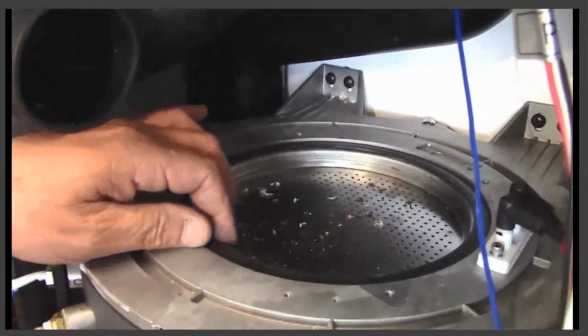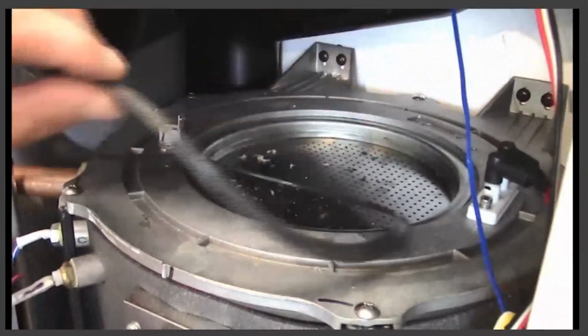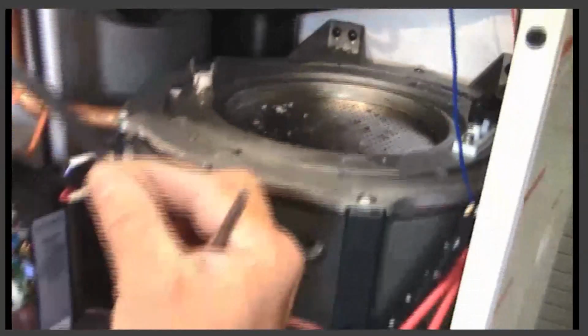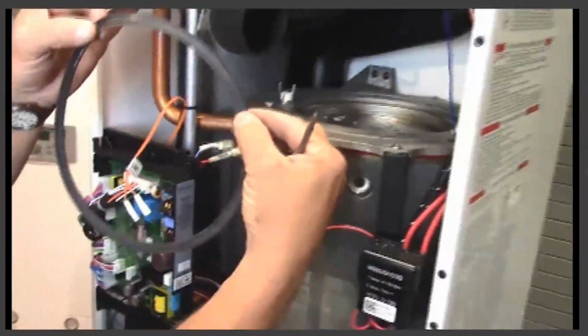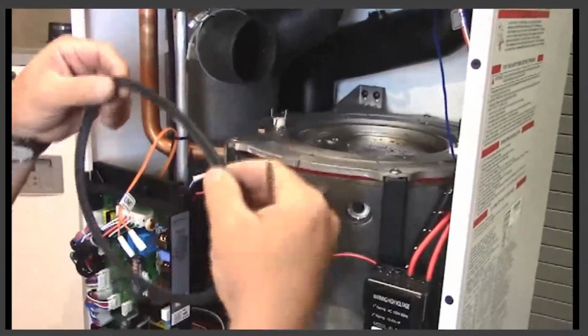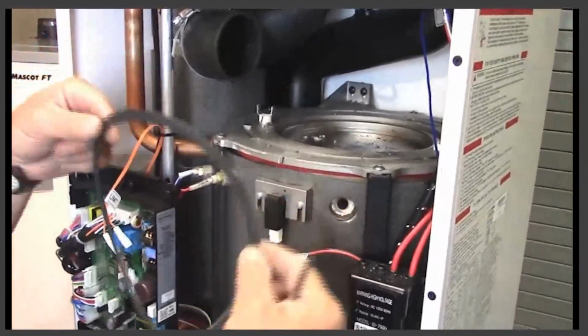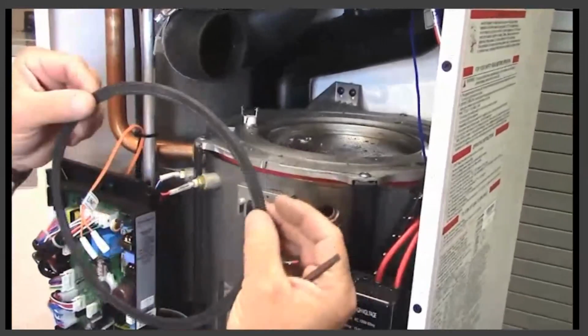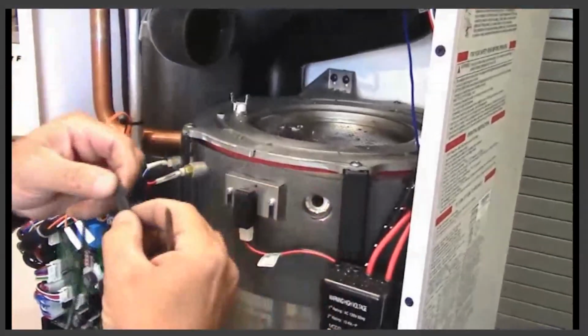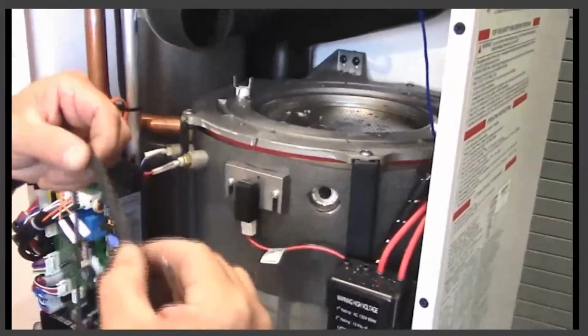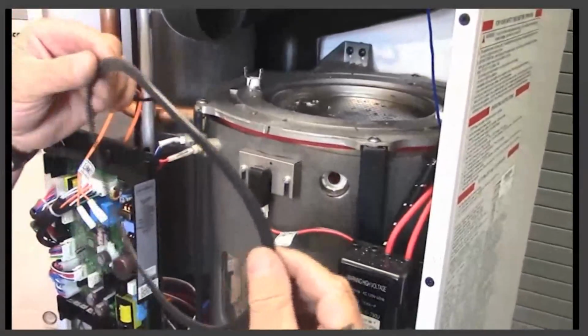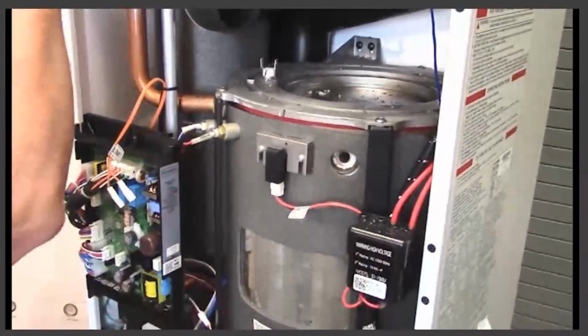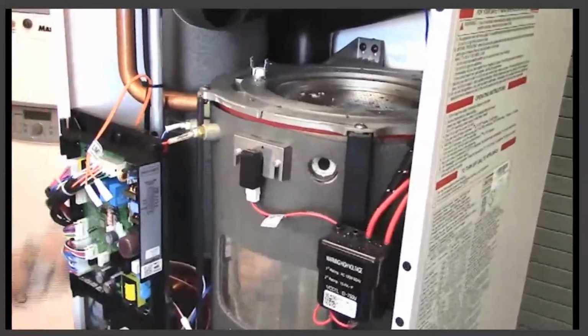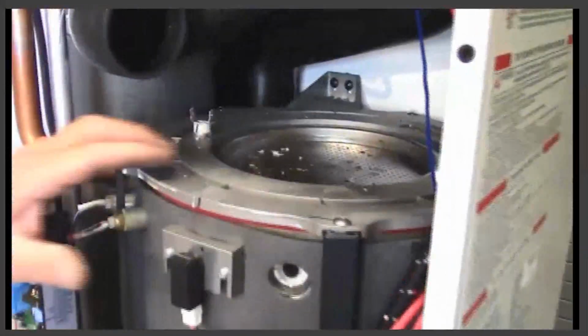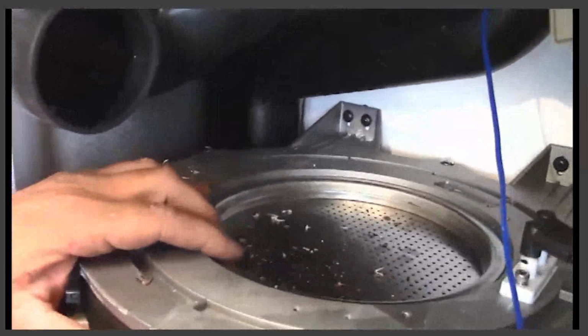Here you're seeing removal of the very large gasket that acts as the combustion gasket on the top of the burner assembly. Inspect that gasket, inspect it for cracks, crimps, flattening out. If need be, replace that gasket before reassembly. And that gasket has to be in position correctly, or you could get a potential gas leak in the cabinet.